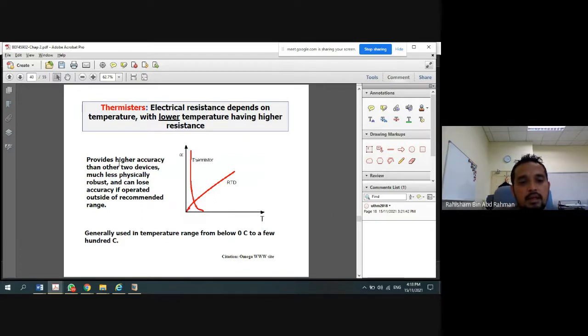This is also high accuracy, much less physically robust, and loses accuracy if operated outside the recommended range. It means that if you operate at a range that is not suitable, it will not be accurate. So it needs to be used in the appropriate parameters. Okay, that is a thermistor. That is also an electrical resistance device based on the temperature, same as the RTD. It is just different in terms of the relationship here. This one is almost linear and this one is exponential. With low temperature, it will have high resistance.